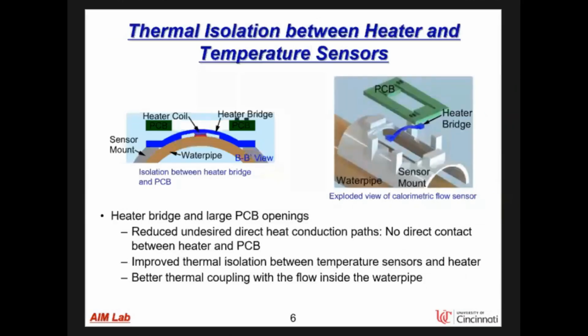And so the thermal isolation between heater and temperature sensors to minimize direct heat transfer between them is essential for effective detection of water flow. The use of heater bridge and large opening in the PCB avoids direct contact between the heater and the PCB and minimizes undesired direct heat conduction paths. This significantly improves thermal isolation between the heater and temperature sensors, allowing better thermal coupling with the water flow inside the pipe to facilitate thermal flow detection.